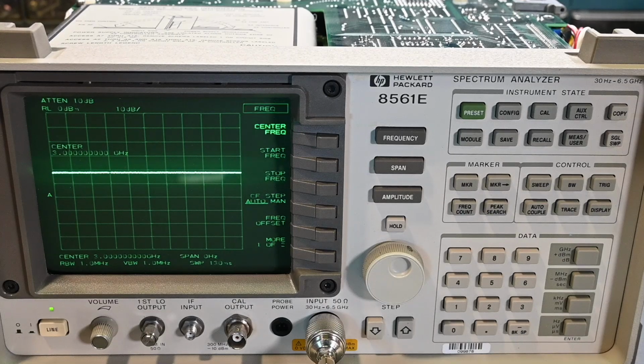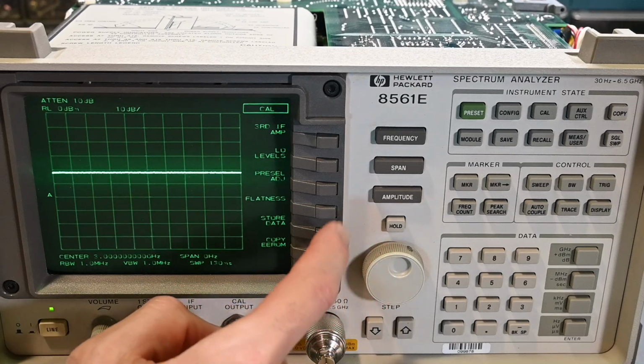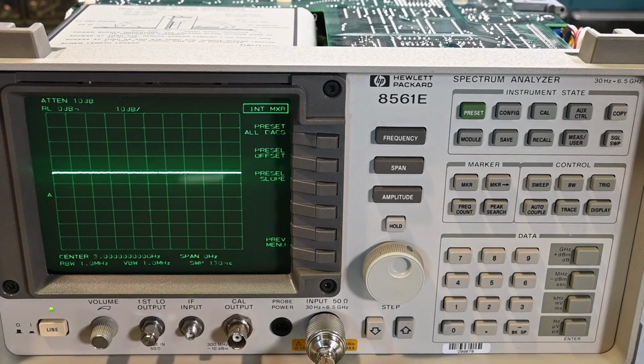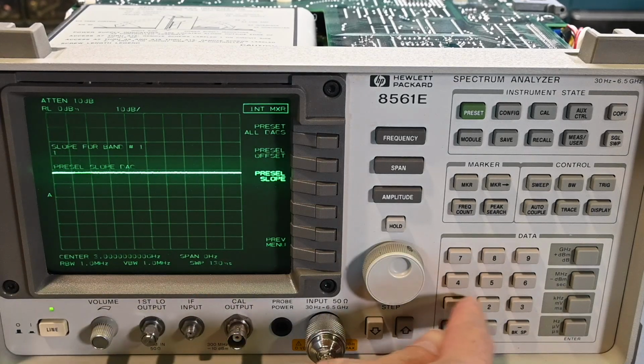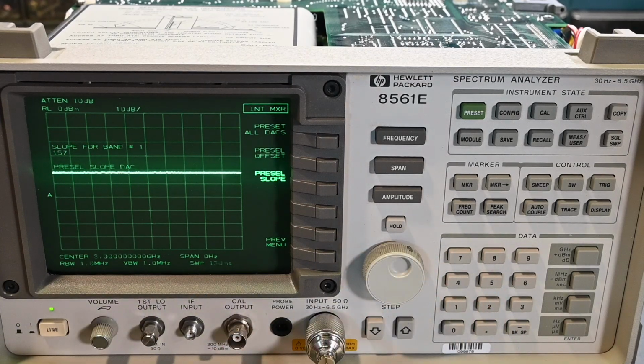In the spectrum analyzer, press cal. So we'll do that. 1 of 2. Service cal data. Pre-select adjust. Pre-select slope. Key in the slope value noted in step 9 above. So it was 157, so it's already there, but we'll just do 157. And pre-select, okay, so 9 above. I did that, enter that. It's going to be an enter. Okay, there it goes. Okay, perfect.